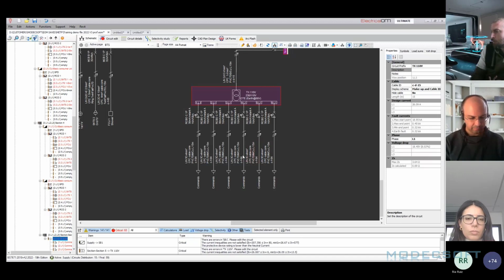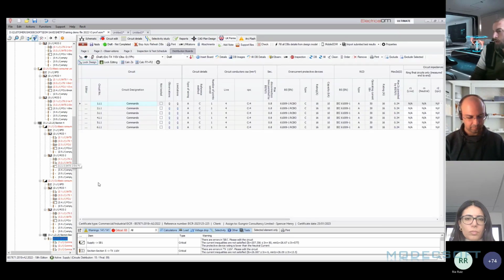When testing these types of cables, they wanted to be able to record 2 sets of results, from each 55 volt line back to our reference earth point. So for any circuit which is a 3-phase circuit, a 2-phase circuit or even a split phase 110 volt system, you can select the circuit on a particular board or in a particular location.